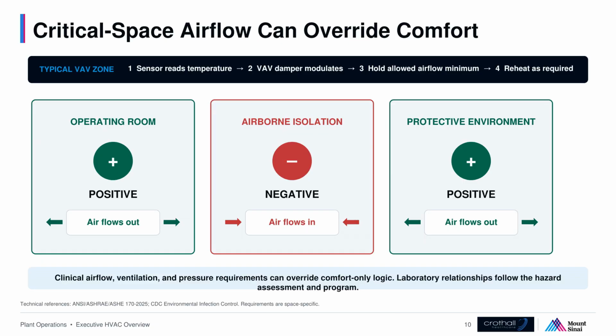At the zone level, the VAV box fine-tunes airflow and temperature. A sensor reads the room temperature, the damper modulates, the box maintains its allowed minimum airflow, and reheat operates when the space needs heat. In an ordinary comfort zone, airflow can often reduce as the cooling load falls. In a critical space, ventilation and pressure requirements may set a higher minimum.